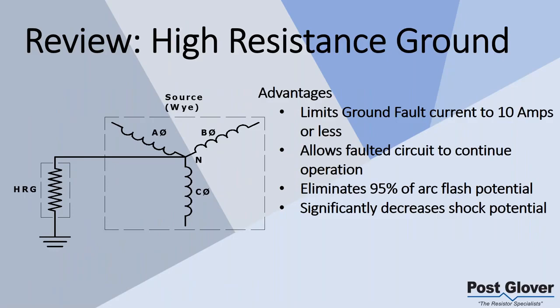So we start off with high resistance ground. This diagram would represent either a high resistance ground or a low resistance ground. Essentially, with your Y point source, you have a resistor in series between neutral and ground. If you have a delta system, you could derive a neutral here, but it's a neutral derived resistor off of the ground point. So it's neutral to ground, neutral resistor ground.